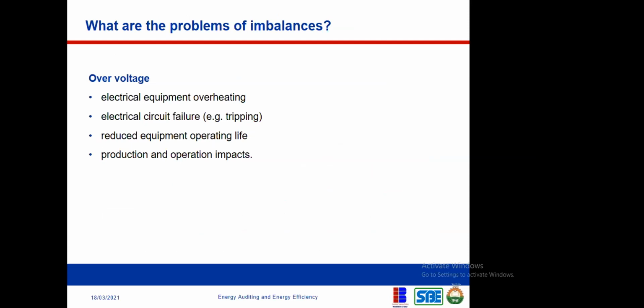So what are the problems of imbalance phases? Let's look at overvoltage. When your imbalance phases are on the high side, we have overvoltage across your lines. The problems that could happen: electrical equipment overheating, electrical circuit failure, your electrical system tripping because of the overvoltage, reduced equipment operational life, and production and operation impact. It can also impact your production processes, and it might even get to a point where your equipment refuses to function or begins to function abnormally. These are the problems of overvoltage. Next we'll see the effect of undervoltage.